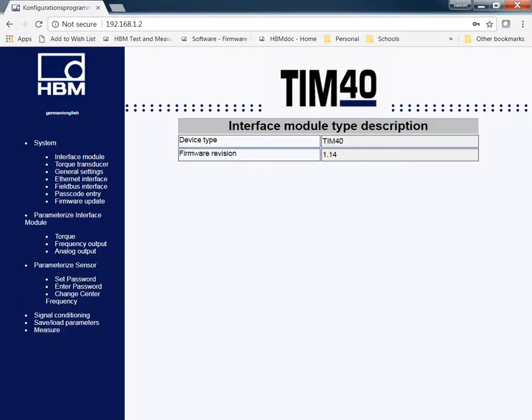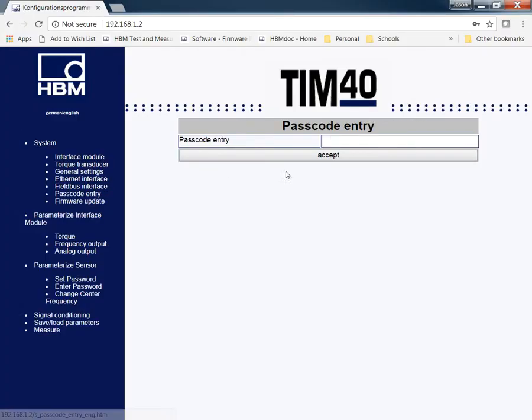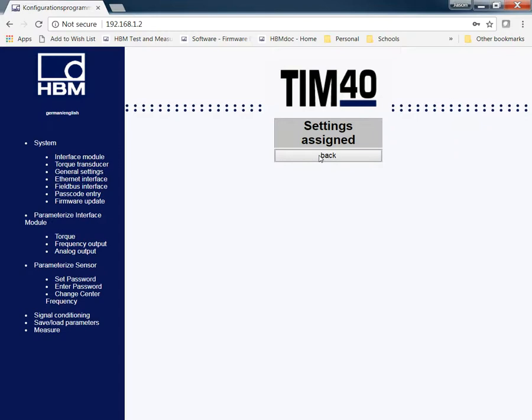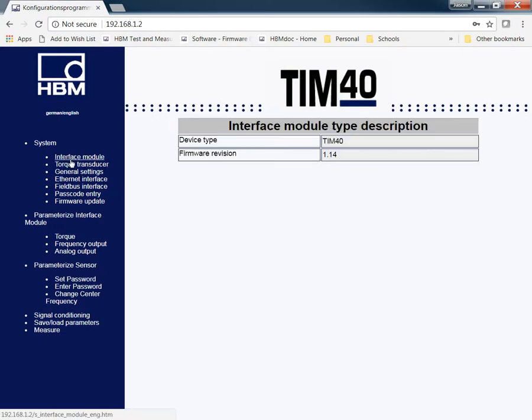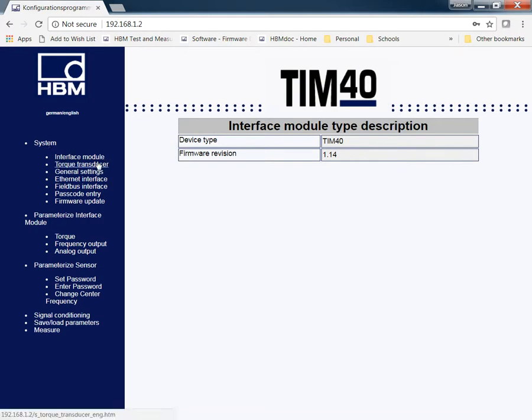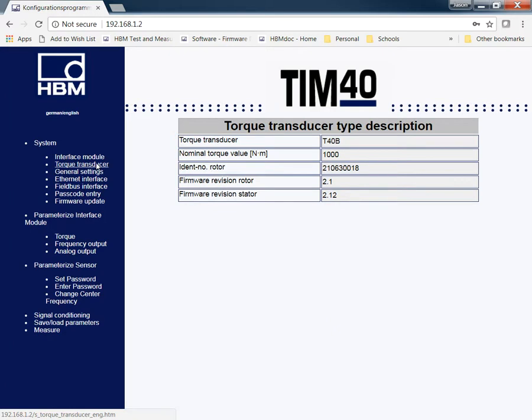When you initially plug in, the passcode is 0123. This is the default password that customers have. I'm going to step through this. This will give you the firmware of the device under the System Tabs Interface Module. Torque transducer, it's going to list what torque transducer I have. Like I mentioned, I have a T40B 1000Nm, and it will also give you the rotor ID as well.